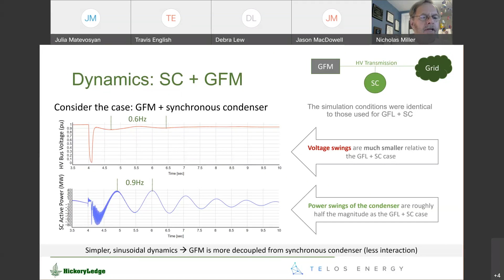So in summary of the findings of this little exercise that I just showed you, we saw that particular rendition of the grid following inverters had similar stability limits around normal disturbances to the synchronous machines. We found that this particular grid forming inverter was noticeably better with more benign swings and was tolerant of a weaker system. We found that the locations for faults were very sensitive when we're talking synchronous machines, but less so for inverter-based resources. Similarly, less dependence on the time. And then there's a bunch of observations about location, et cetera.